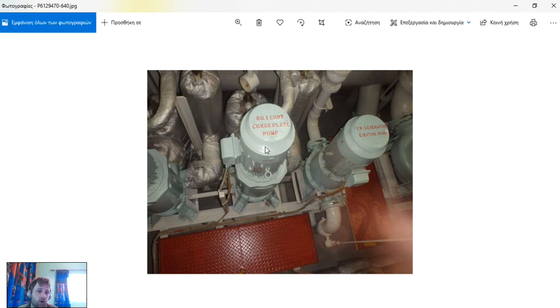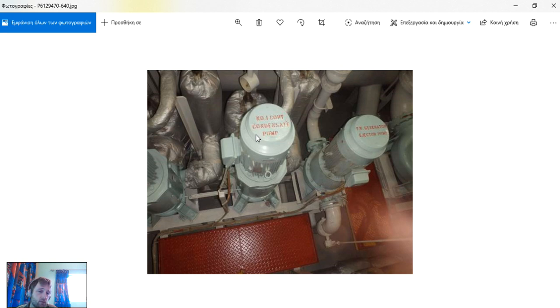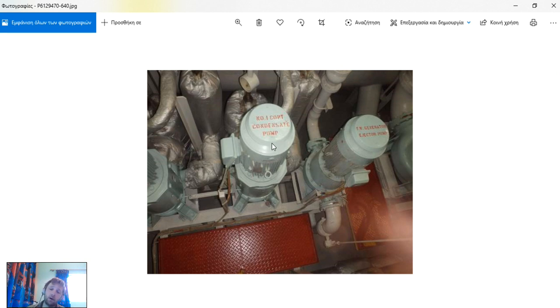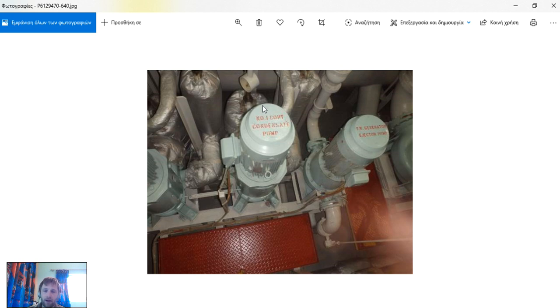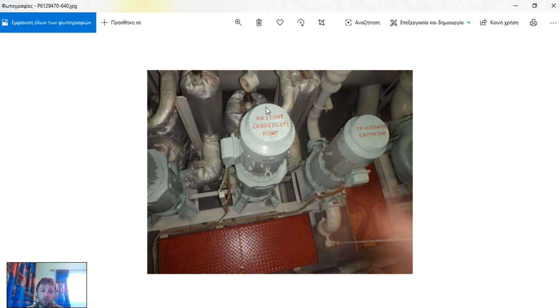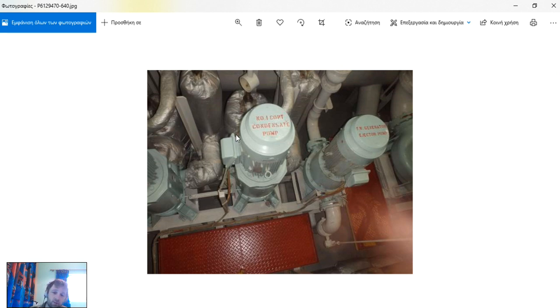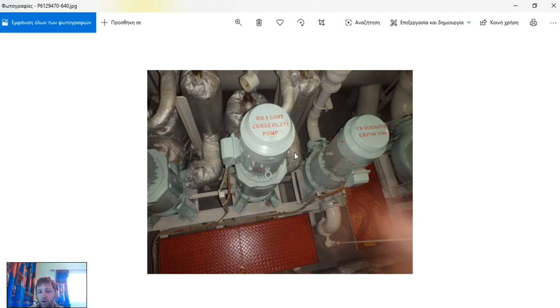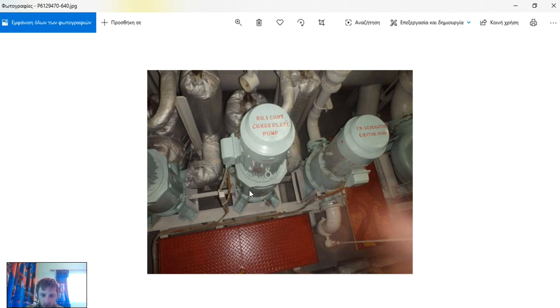We have also our condensate pumps here which drag the condensate from the condenser and deliver it to our cascade tank. The water which was previously steam is accumulated on the bottom of the condenser. There is also a level controller which controls the level inside to protect the tubes and also to protect the pumps, ensuring they always have suction. That's why these pumps are placed on the bottom and below, so they will always have positive pressure suction and avoid gravitational effects.